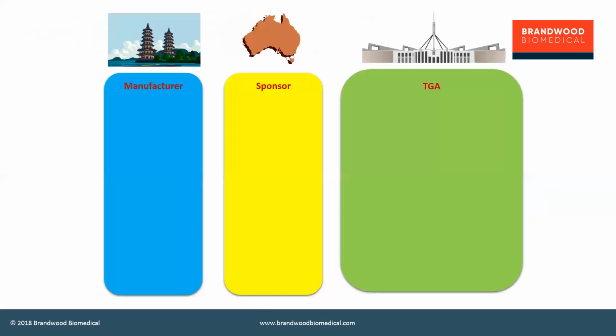So we have three parties involved: the original manufacturer of the device, the Australian sponsor, who has to be a legal entity within Australia to deal with the TGA, the equivalent of a European authorised representative or a market access holder in other markets. And there must be a legal sponsor in Australia because that's who TGA controls. And then there's TGA itself, based in Canberra in the national capital.